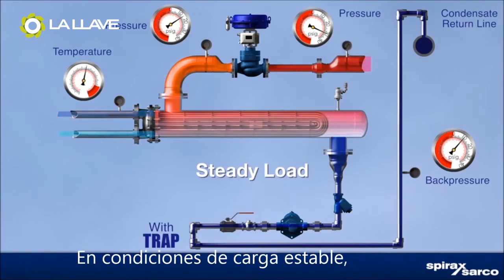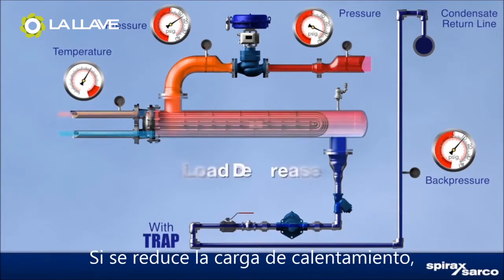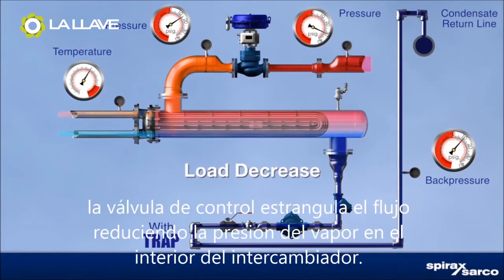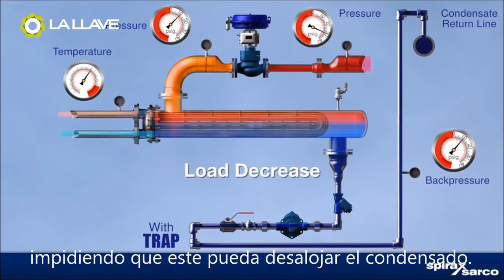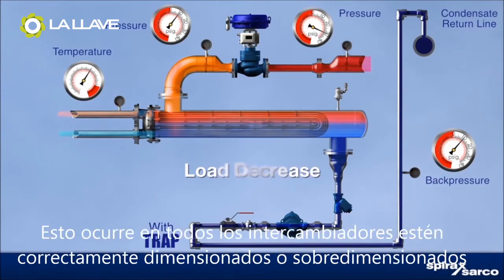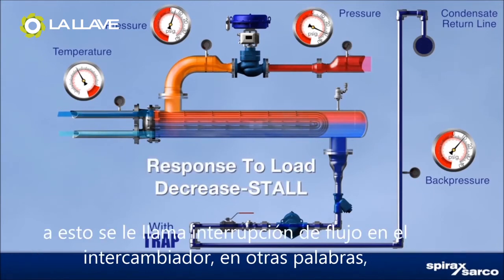Under a steady high load, differential pressure removes the condensate from the heat exchanger. Under reduced heating load, the control valve throttles down, reducing the steam pressure inside the heat exchanger. This also reduces the differential pressure across the steam trap, making the trap unable to remove the condensate. This happens in all heat exchangers whether properly sized or oversized, causing condensate to flood the steam space — known as heat exchanger stall.